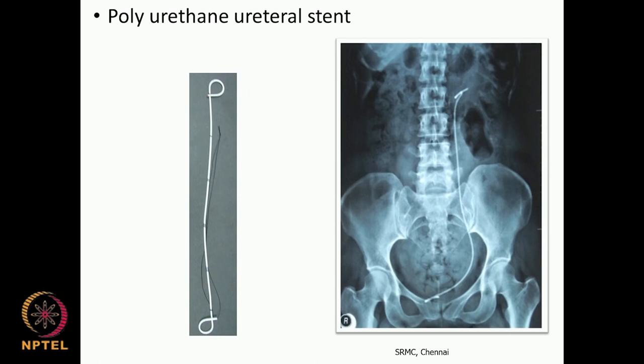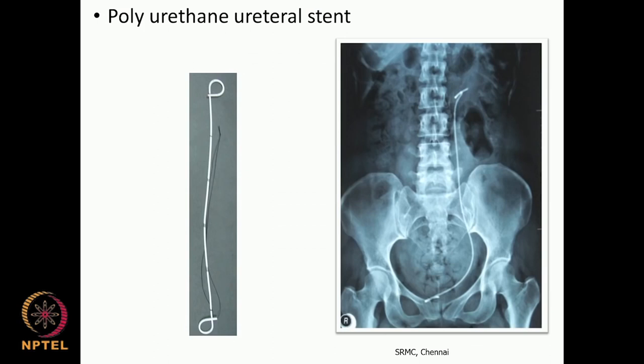The environments are also very different. The polyurethane faces a urine environment with several salts like calcium oxalate and bacteria like E. coli, Proteus, and Morganella — a very harsh environment. In the bone environment there is generally no bacterial infection, no salts — only exposure to blood, plasma, and protein. The stainless steel implant must stay for several years in a mild environment, whereas the polyurethane stent must withstand a very harsh environment for only four to six weeks, and should not allow salt precipitation or enhanced bacterial infection.